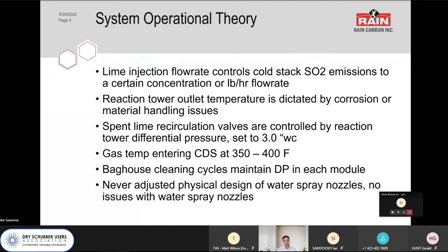The gas entering the CDS out of our economizers, which we have at both sites, is around 350 to 400 degrees Fahrenheit, depending on how long the boiler has had since its last cleaning. Our baghouse cleaning cycles maintain differential pressure in each module individually. So there's a high and a low pressure DP in each module, and the baghouse will pulse until the low DP is reached and stop pulsing until the high DP is reached.